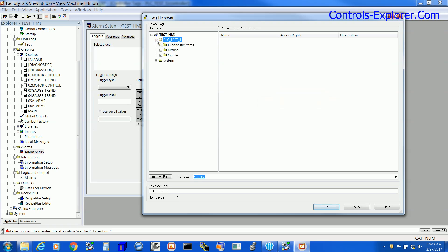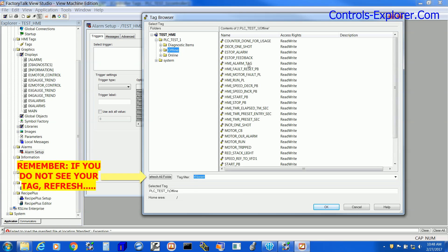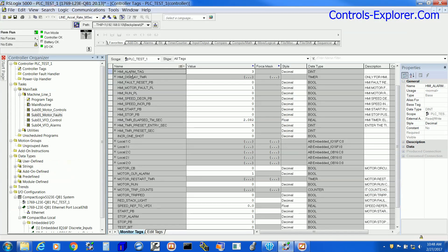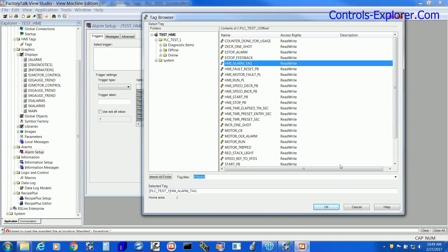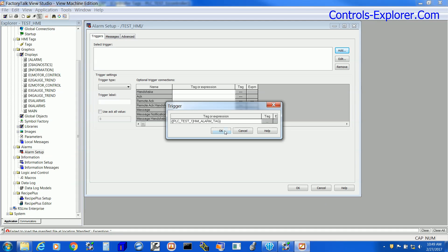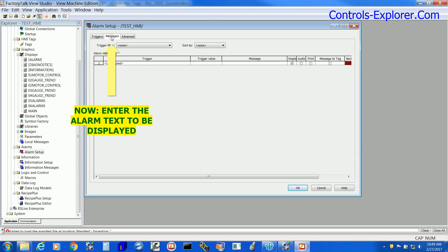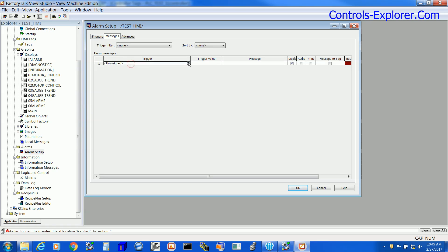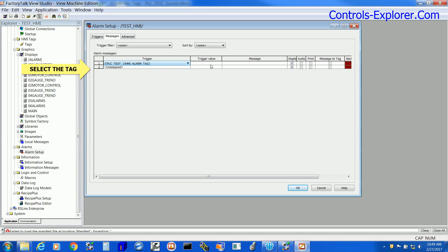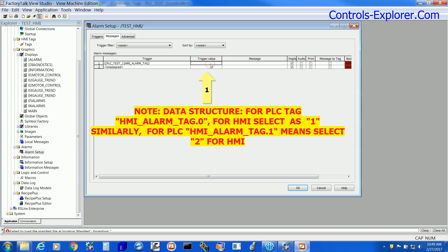If you do not find your tag, please refresh it. This is the HMI Alarm Tag which is a double integer, and we have added this HMI Alarm Tag. Next we have to change it to bit, that is 0 to 31, and this is where we are going to type our alarm text. The trigger value should be 1, and a key point to note: when in the PLC the tag is bit 0, in the HMI it is bit 1.